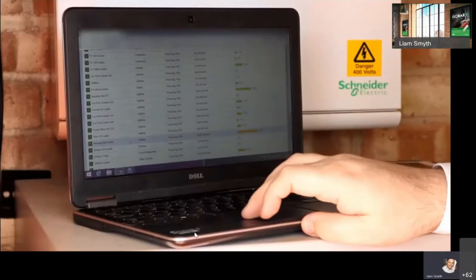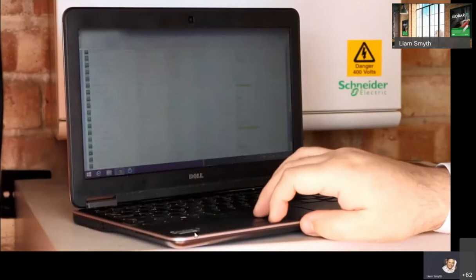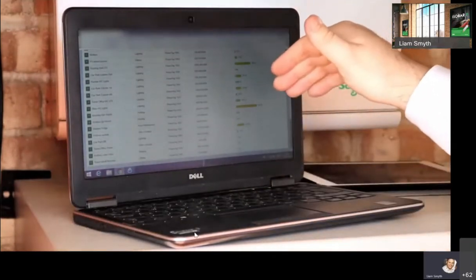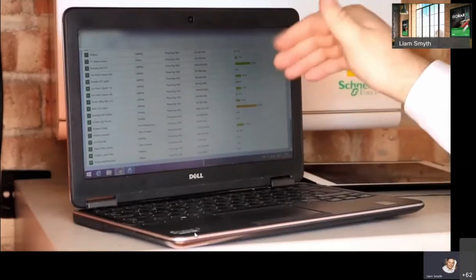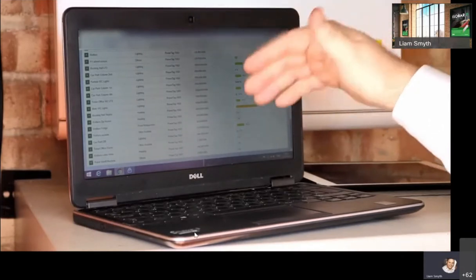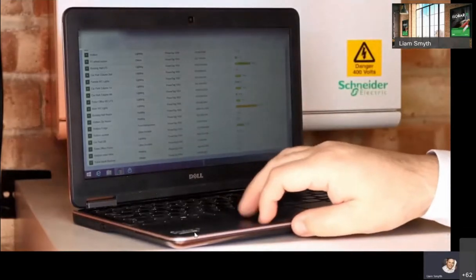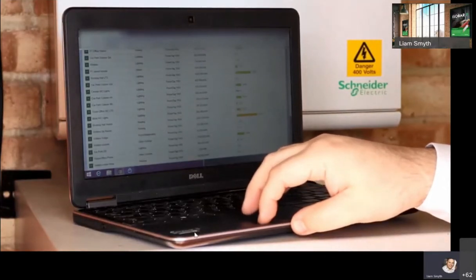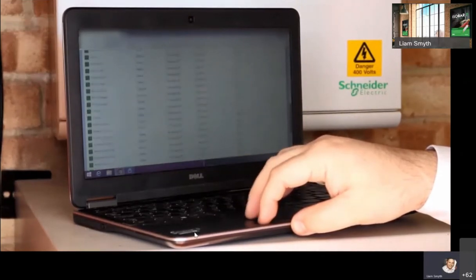I can then look at heating, booking hall heaters on, 52%. So it actually gives you a breakdown. Now, if, for instance, I had a 20 amp breaker and I was at 16 amps, that would be near to a threshold where it could possibly trip based on inrush currents. So I can program this to email me when it gets near to the threshold, which is quite a unique feature, because you effectively can look at the dynamics of how your circuit is designed, look at the loading of how your circuit is designed, and then adapt the alarms to suit, which is quite a good feature.